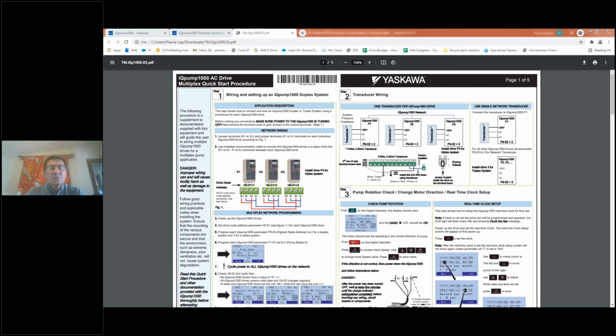to basically achieve the same flow and pressure regulation. Now, that inherently makes sense. Do we drive the cost up? We do. If I have 4 200 horsepower drives versus one 800 horsepower drive, I have a single point failure on the 800 horsepower drive, but I have less real estate used, less wiring, less installation costs, and to be perfectly honest with you, the overall cost is less also.